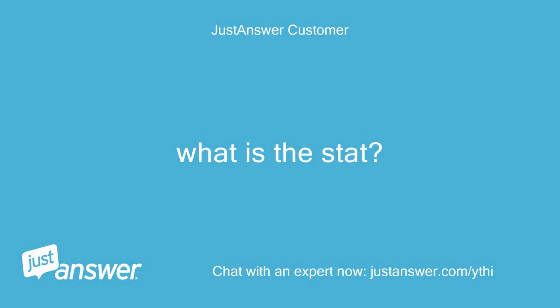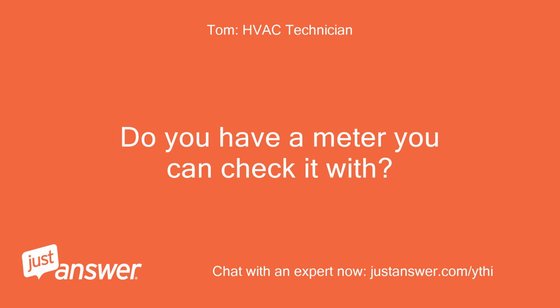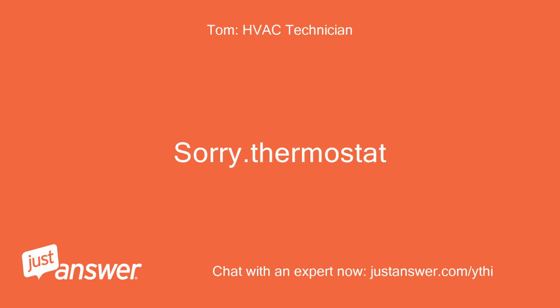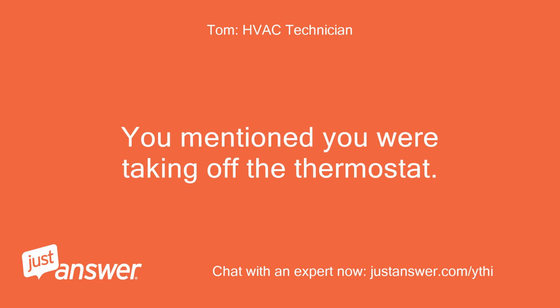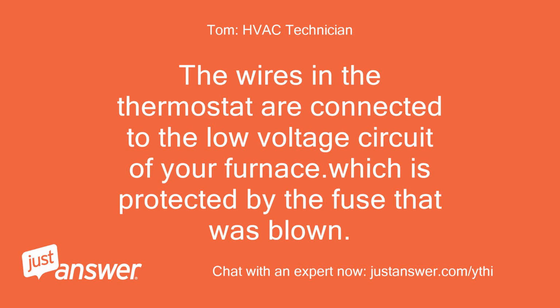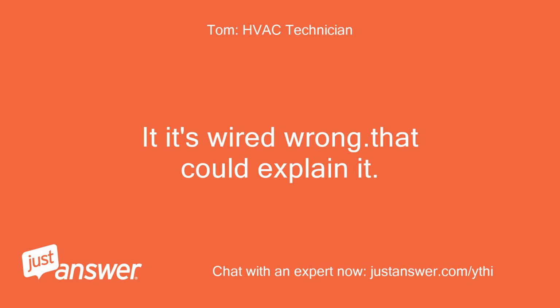What is the stat? Do you have a meter you can check it with? Sorry, thermostat. You mentioned you were taking off the thermostat. The wires in the thermostat are connected to the low voltage circuit of your furnace, which is protected by the fuse that was blown. It's wired wrong, that could explain it.